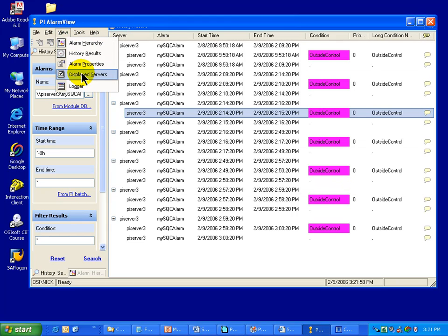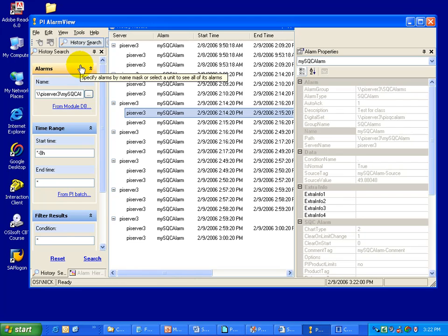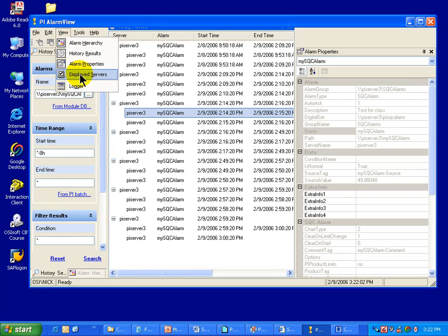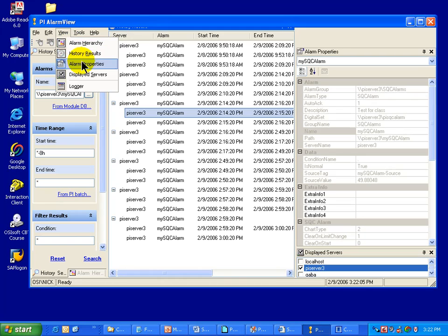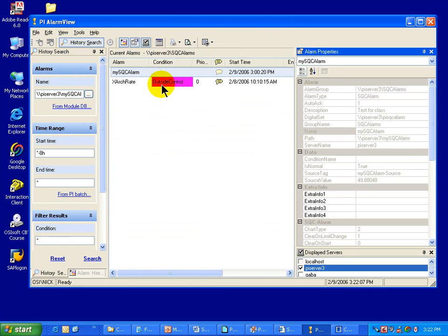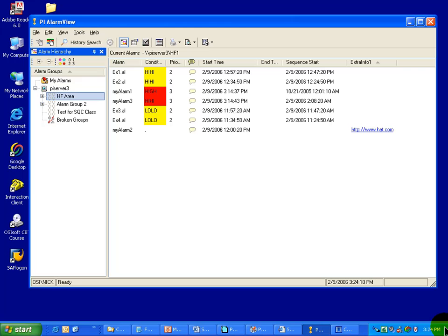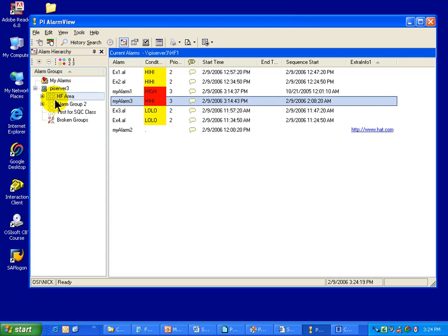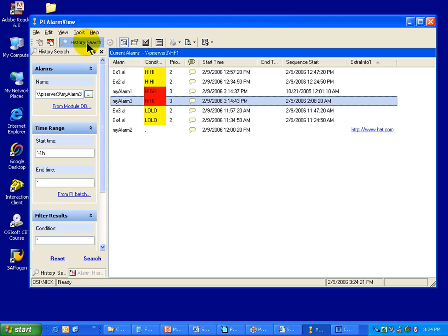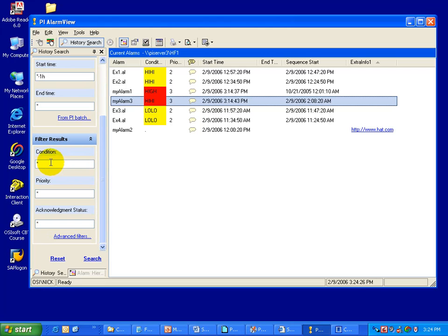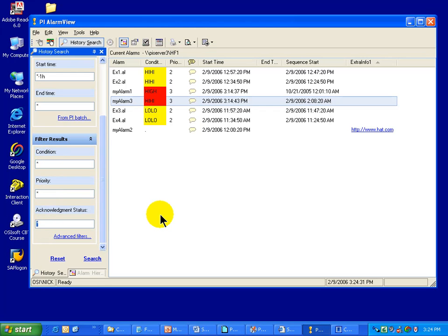I can turn those panes back on by choosing View and looking at the properties, displayed servers, etc. When searching through history, you can also filter for certain priorities, alarm conditions, or acknowledgement statuses. For example, for this tag MyAlarm3, I can search its history and filter based on an alarm condition, an alarm priority, or an acknowledgement status.